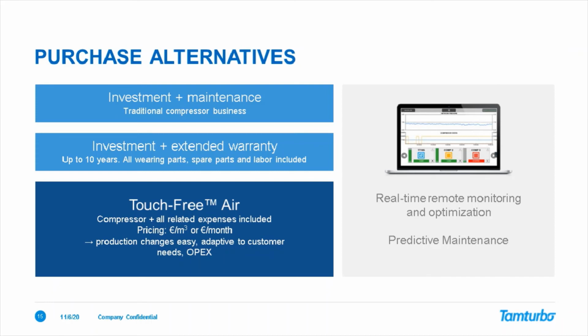And we can do that because all of our units are remotely monitored, so they all have a 3 or 4G modem in the unit, and our technical support team is keeping an eye on the compressors and actually optimizing the compressor usage if there are production changes in the factory. So they are always optimizing how the compressor is operated remotely, unless the customer, of course, says that we cannot do it, but we can.